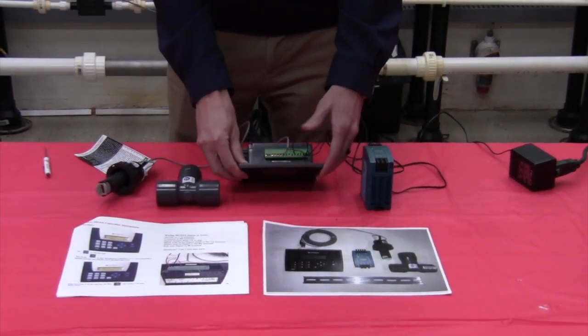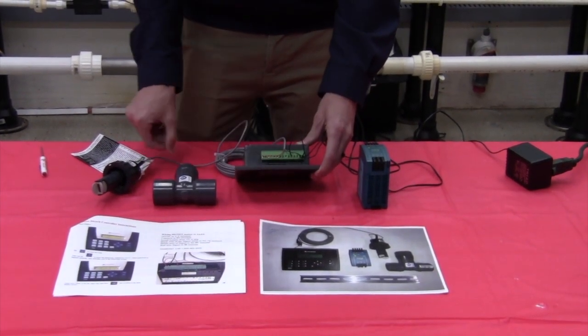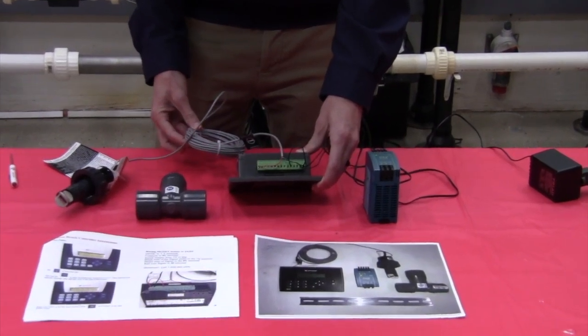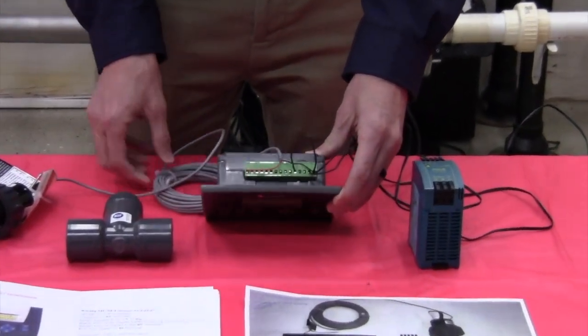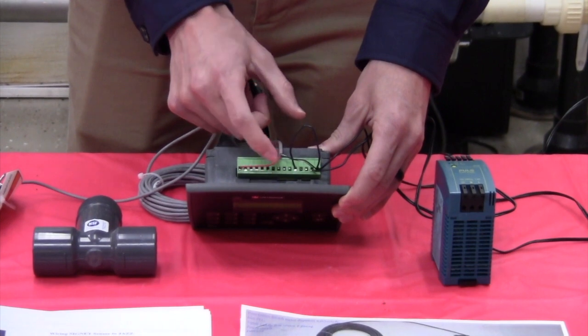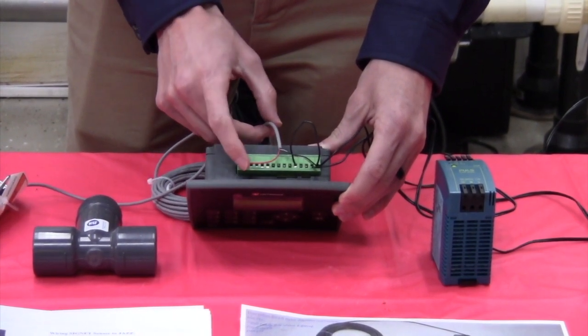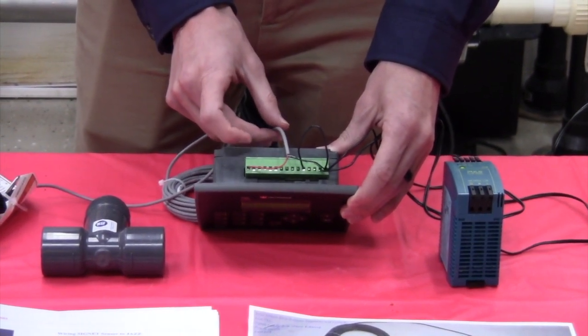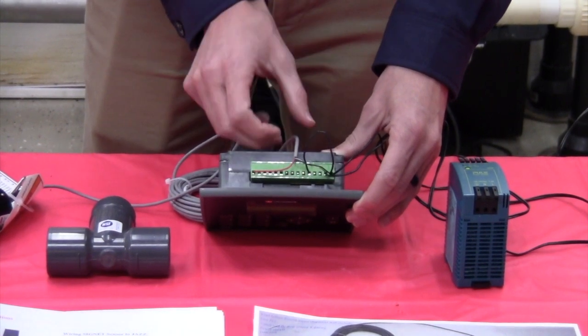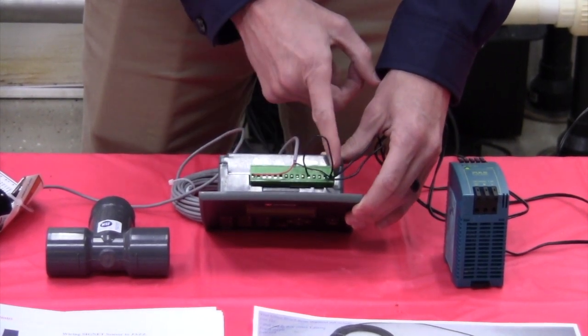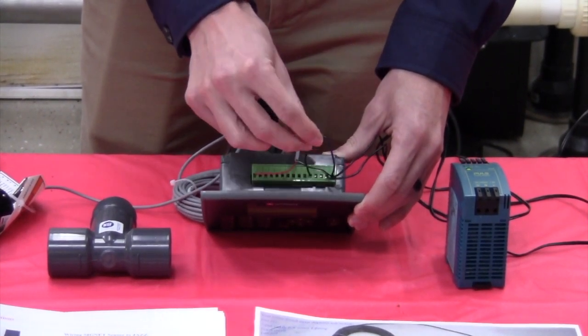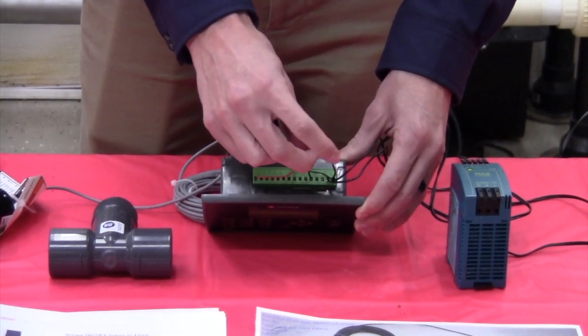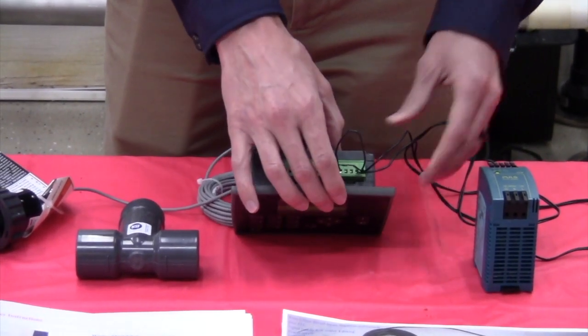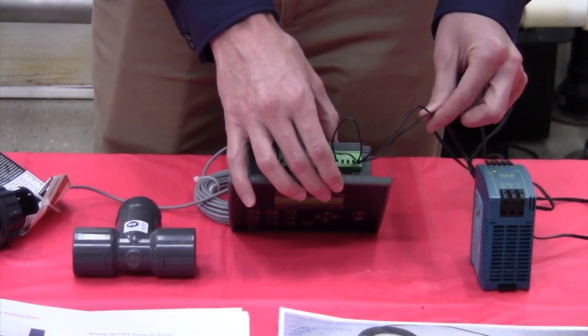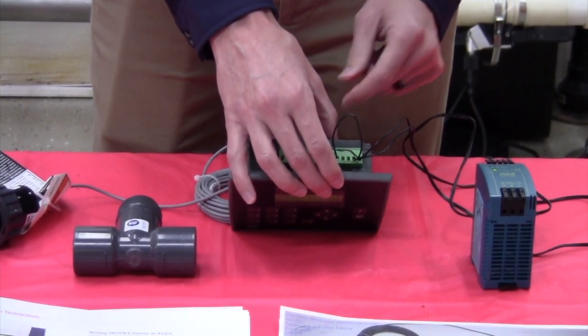If I flip my PLC over here, I have the gray cable coming from my paddle wheel flow meter that's 3 conductors: a red, a black, and a shield. The red lands on terminal 15, the shield lands on terminal 2, the black lands on terminal 1, and then I also have a jumper cable that goes from terminals 1 to 5, and the 2 leads coming off my power supply go to terminals 1 and 2.